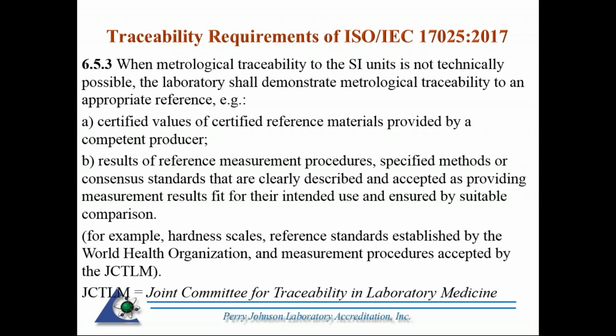Okay, when metrological traceability to the SI is not technically possible, the laboratory shall demonstrate metrological traceability to an appropriate reference. For example, we have two of them listed here. Again, we have certified reference material by a competent producer, i.e. 17034, for example. Then we have another area here: results of reference measurement procedures, specified methods, or consensus standards that are clearly described and accepted as providing measurement results fit for their intended use and ensured by suitable comparisons.